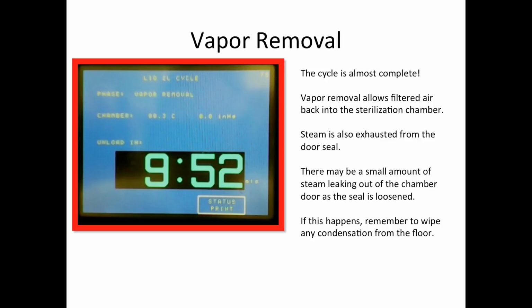But now we have to let air back into the sterilization chamber, and we do that by using the vapor removal phase, when we admit a small amount of filtered air back into the sterilization chamber to bring it back to atmospheric pressure. Steam is also exhausted from the door seal, so there may be a small amount of steam leaking out of the chamber door, and if this happens, remember to wipe up any condensation from the floor.